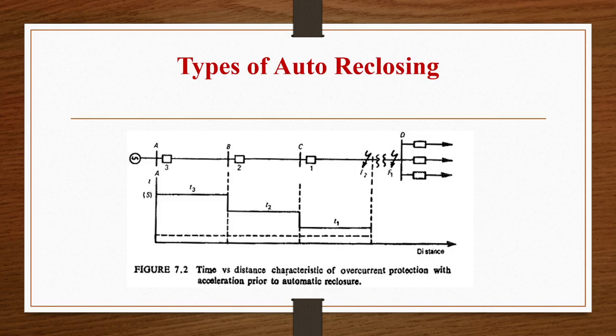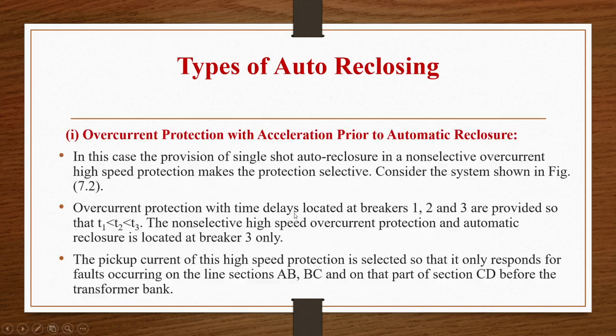We are taking certain conditions here: T1 is less than T2 which is less than T3. The non-selective high-speed overcurrent protection and automatic reclosure is located at circuit breaker 3 only. The pickup current of this high speed protection is selected so that it only responds to faults occurring on the line sections AB, BC and on that part of section CD before the transformer bank.